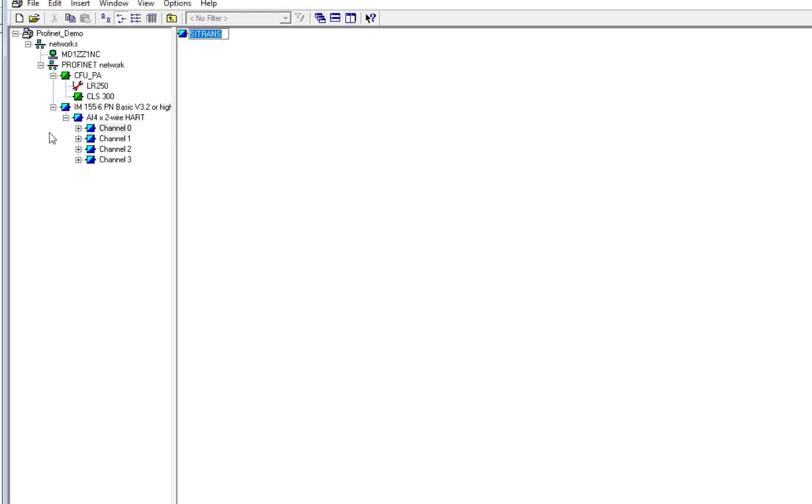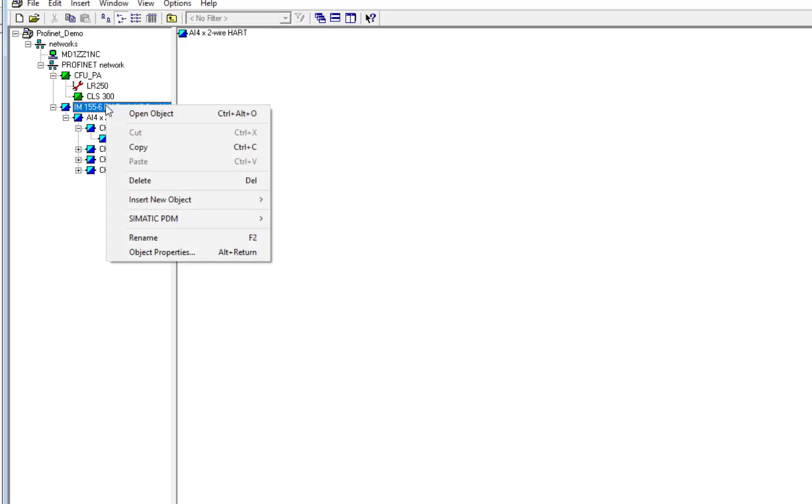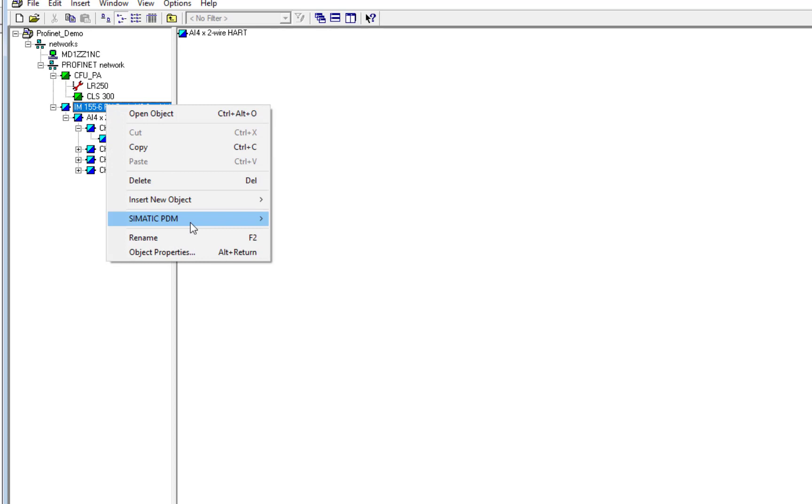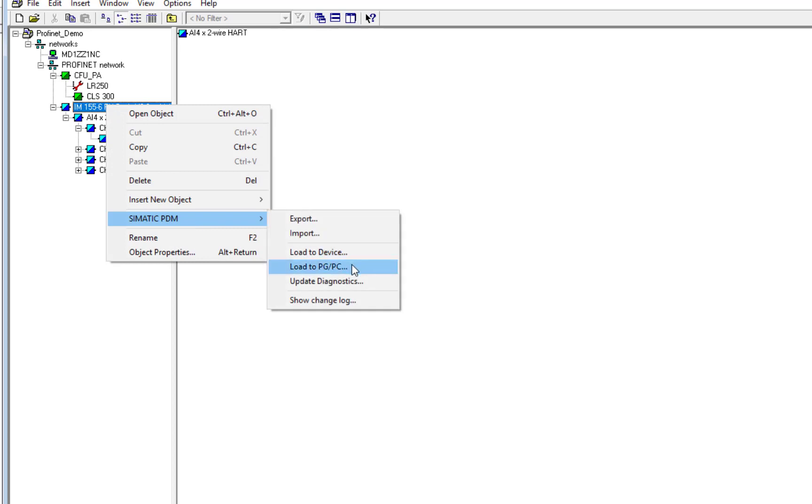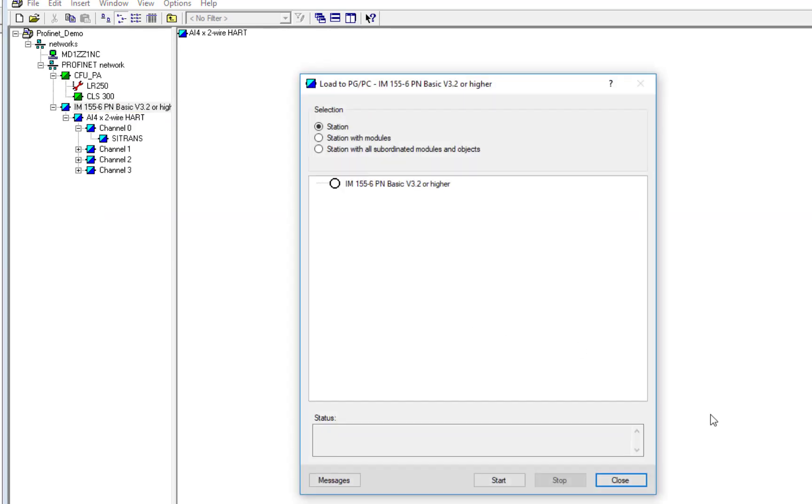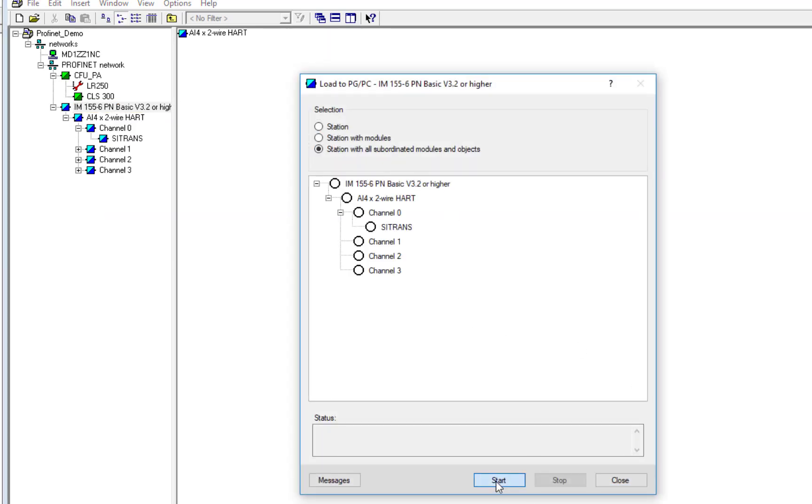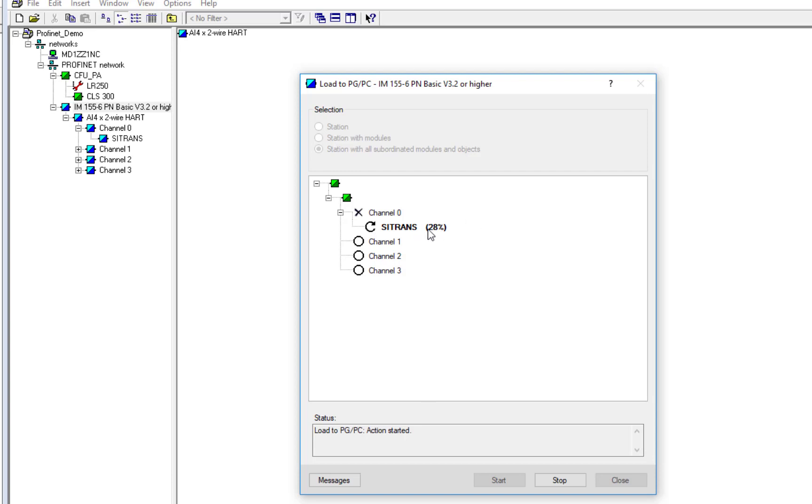And we can do the same again with this. So if we right-click up the top, PDM, Load to PG. Select all the subnetworks, and it will read the parameters. So here, unfortunately, we are governed by the speed of HART. So it's still a lot quicker than doing Profibus DP to HART. But unfortunately, there's nothing we can do about the upload speeds of HART.